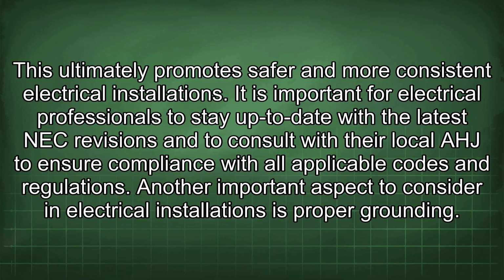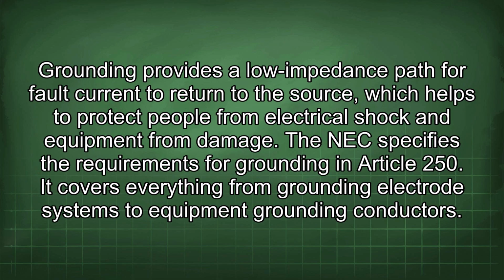Another important aspect to consider in electrical installations is proper grounding. Grounding provides a low impedance path for fault current to return to the source, which helps to protect people from electrical shock and equipment from damage. The NEC specifies the requirements for grounding in Article 250. It covers everything from grounding electrode systems to equipment grounding conductors.